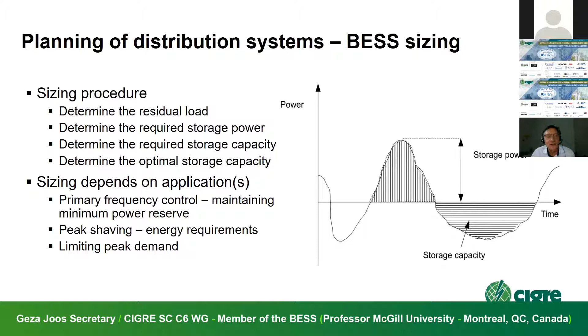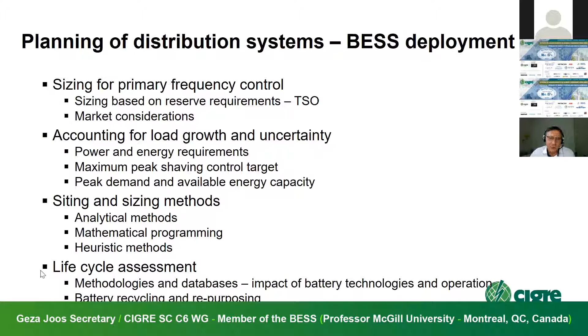One of the important issues today is life cycle assessment, because in power grids we're accustomed to equipment that lasts up to 50 years, if it's a line, even 100. Substations, transformers, 30 years, probably breakers as well. And here we have an element whose life cycle we do not know, but it probably doesn't go beyond 5 or 10 years. The business models, again, I did mention that you have to justify the deployment of battery energy storage systems. So you have to quantify the benefit, you have to make a business case.